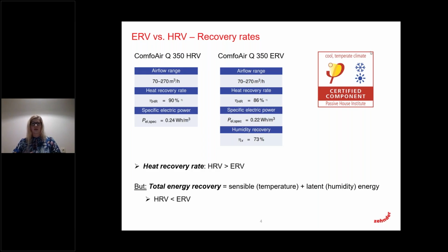And when we compare the total energy recovery, which is sensible heat, temperature, something that we can feel, and latent heat, the humidity, also sometimes called the hidden heat or energy, then the total recovery rate for ERV is higher.